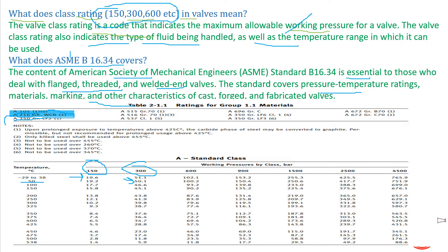First, the material for the valve is known — all materials used in manufacturing of valves are mentioned in ASME B16.34. Based on this, we define our system pressure. As a process engineer, we know the pressure and the temperature at which our fluid is flowing. Based on this temperature and pressure we select the class — whether Class 150, 300, 600, 1500, or 2500 — for a valve.